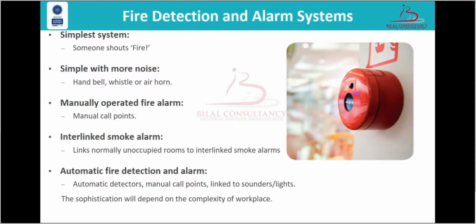But some general principles can be applied. The simplest system is in a very simple, low fire risk workplace where all parts of the workplace can be seen by the occupant and there is no greater fire risk. Then no detection or alarm system may be required. If there is a fire, people will see the fire and shout fire. This may be acceptable as long as the workplace is not so large that some people would not hear that shout. If the workplace is simple and low risk but large enough that building occupants might not hear a shouted alarm, then a hand-operated alarm might be used, such as a handbell, whistle, or air horn.